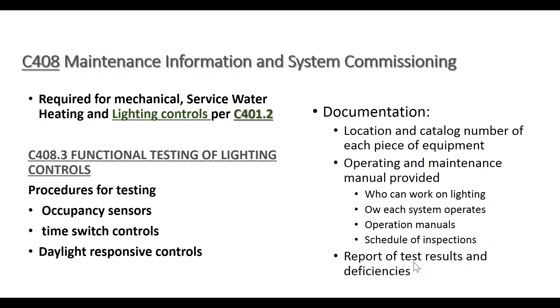It's just that there was never a pointer to 408.3, so a lot of people weren't doing it, but it's always been in there. Occupancy sensors, time switches, daylight controls—they have to be functionally tested to make sure they work, and there has to be documentation of the results. If you go back and look at that commissioning checklist, there's a line item for occupancy or daylight controls, so don't forget that.